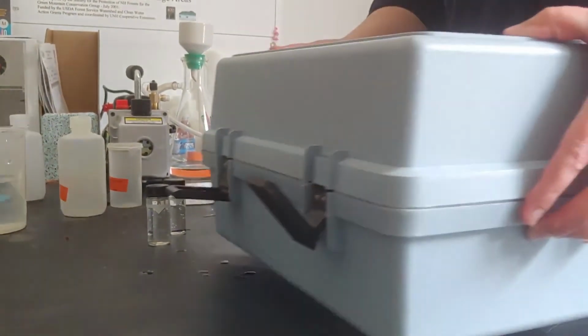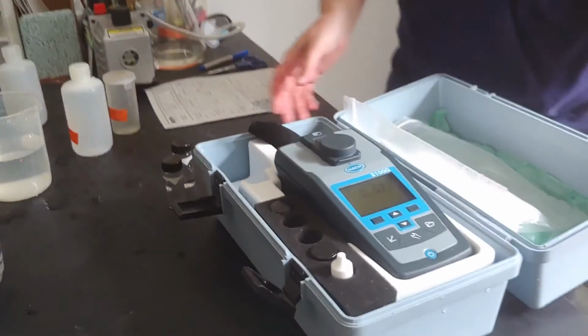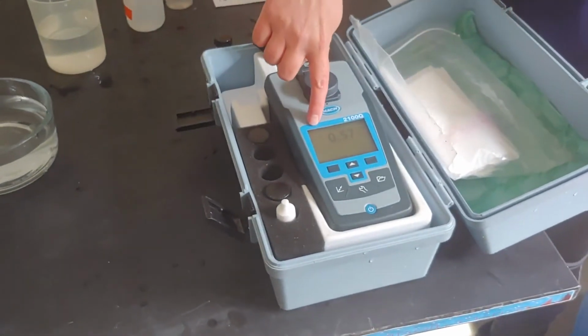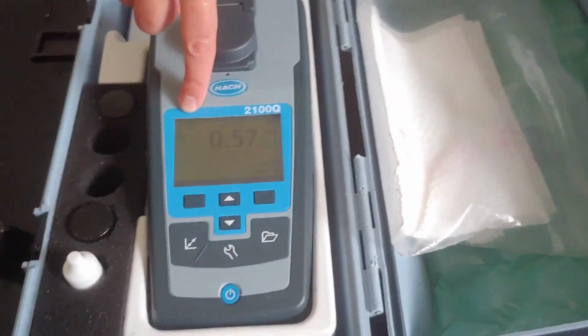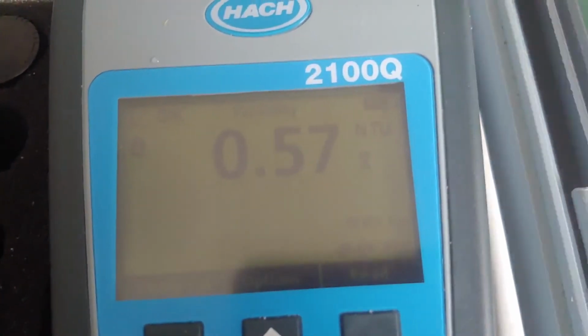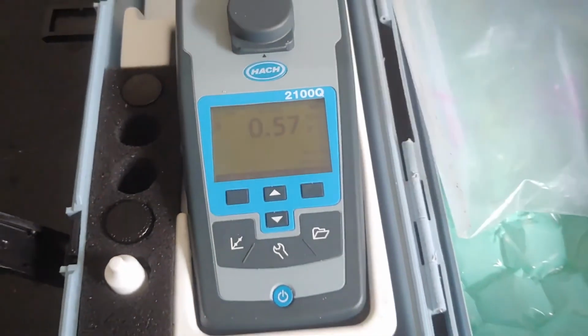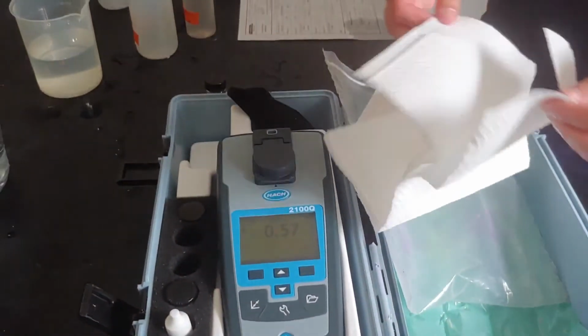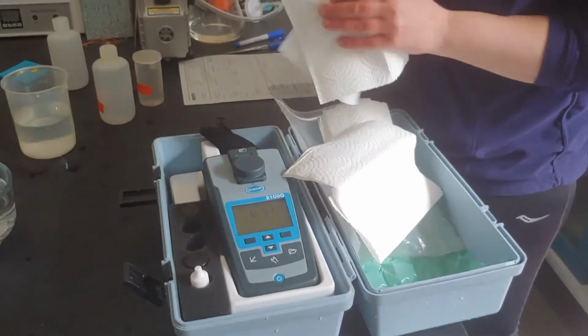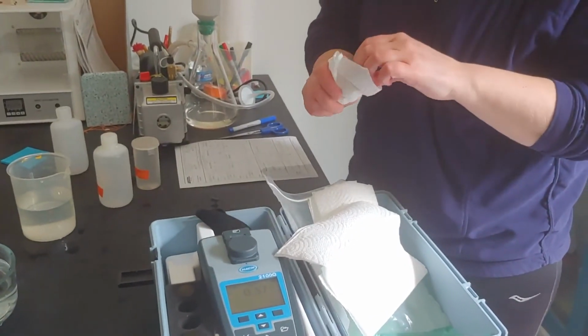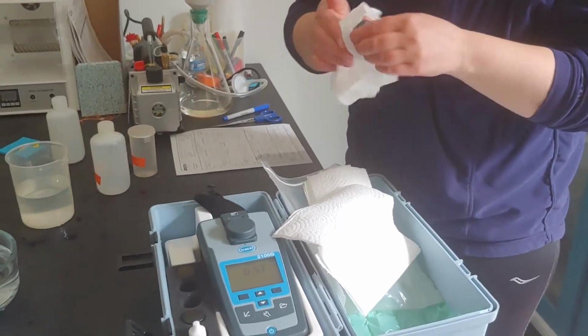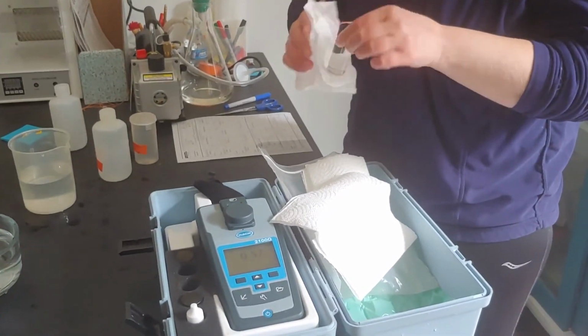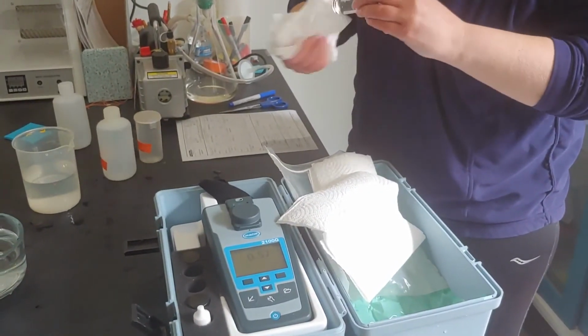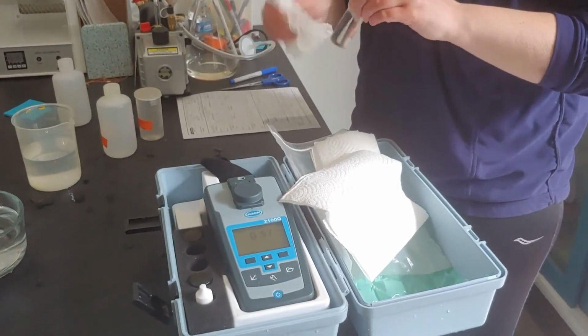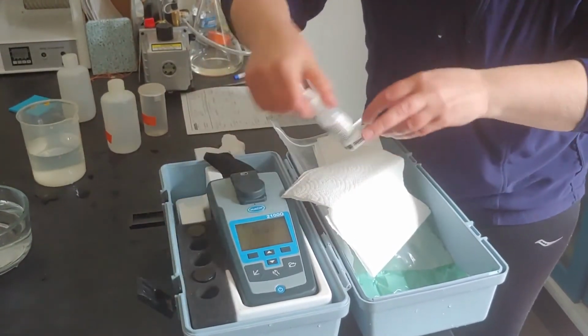From here, what I'm going to do is get out my turbidity meter. Make sure that it's on, and I want to make sure that I'm seeing the OK symbol in the upper left-hand portion of the screen. Once I see that, I'm going to dry my vial off, first with a paper towel. We want to try to get rid of any excess water that may be on this vial because we are going to put mineral oil on it. And as many of us know from when we were kids, water and oil don't mix. So once my vial is dried off, I am now going to take my mineral oil.